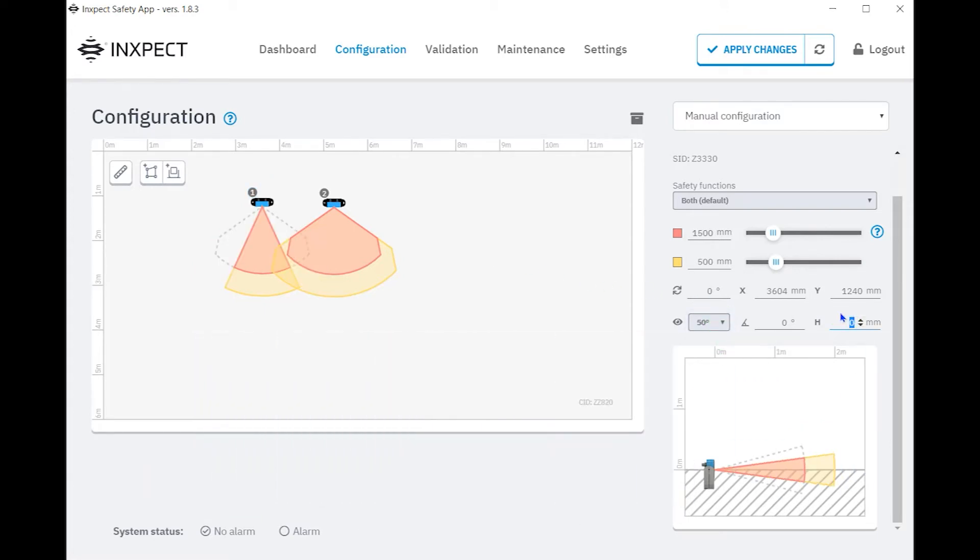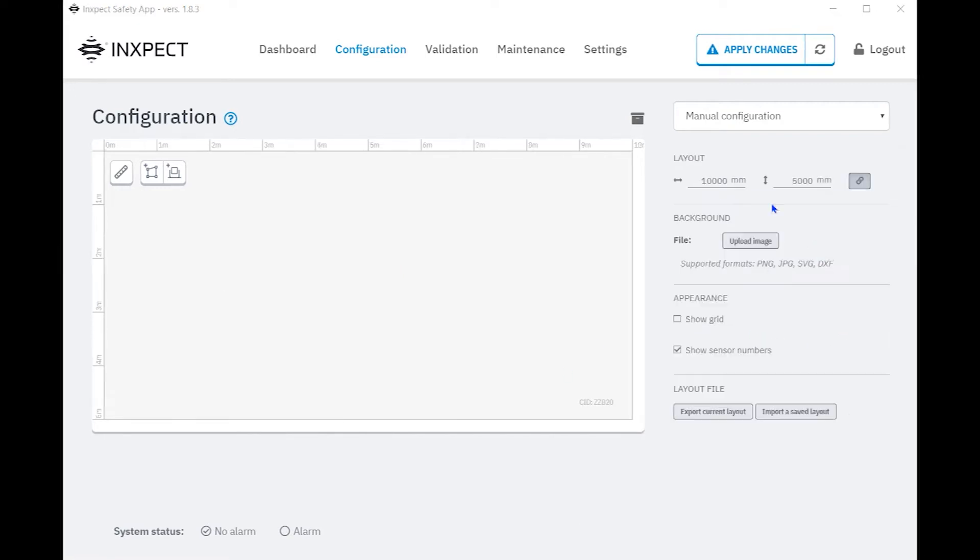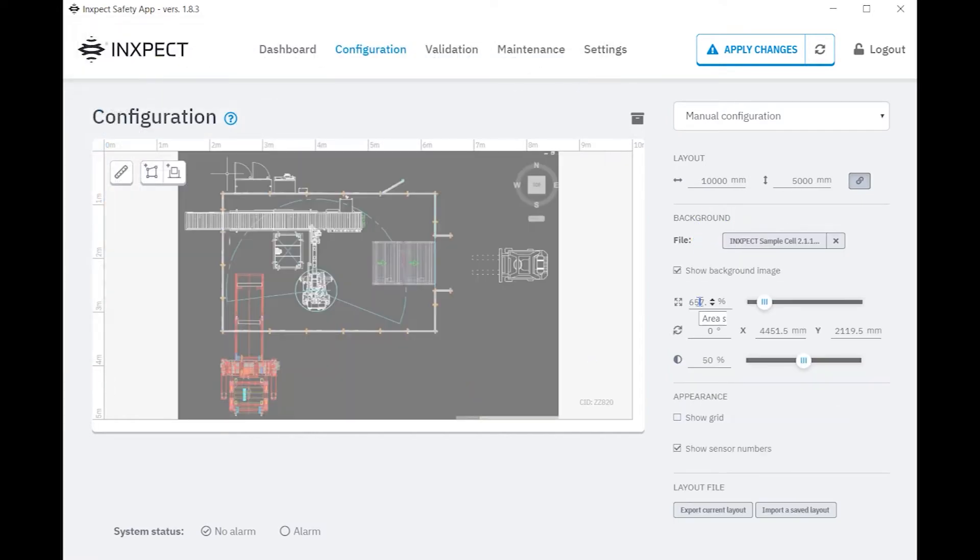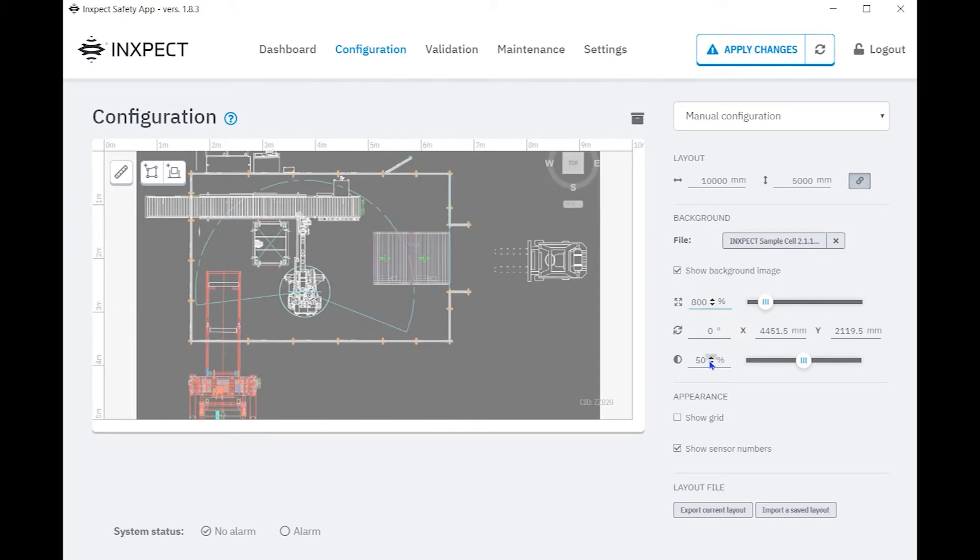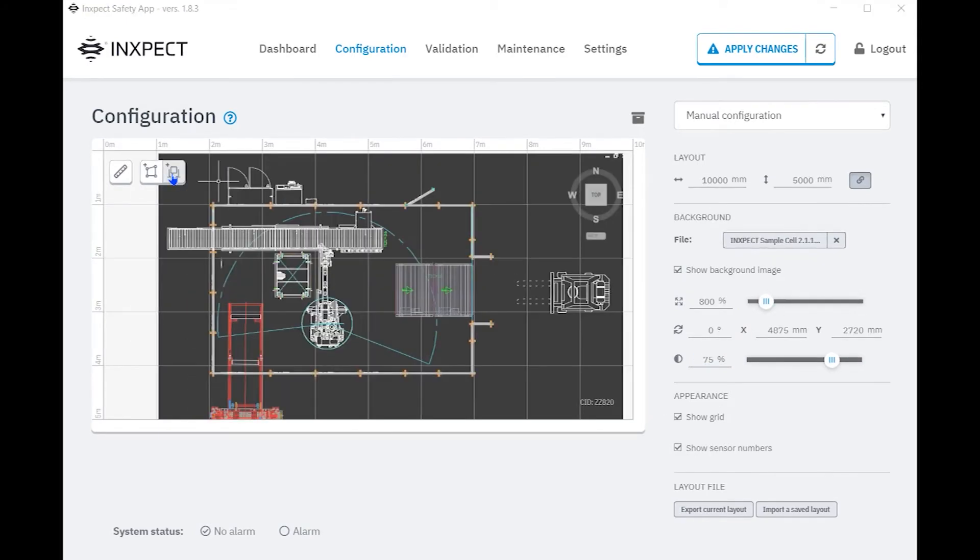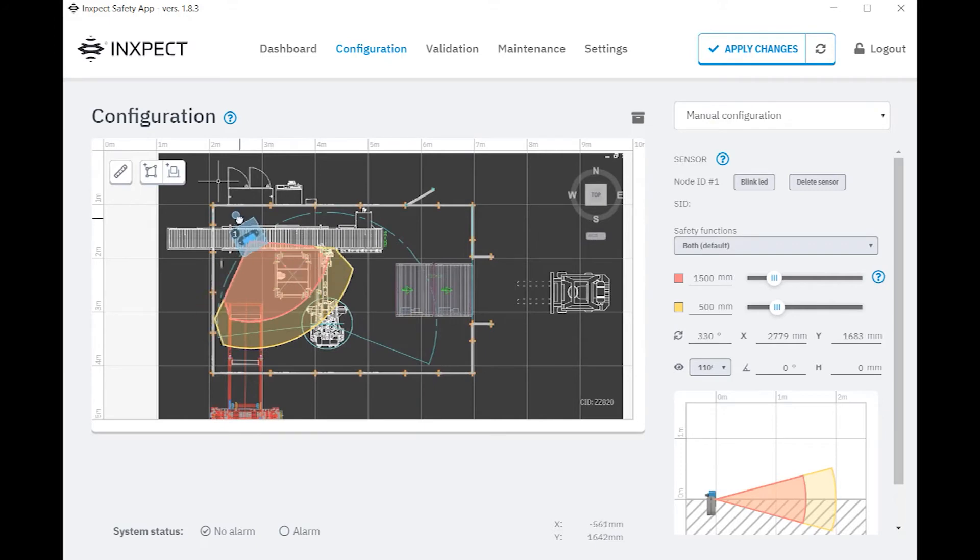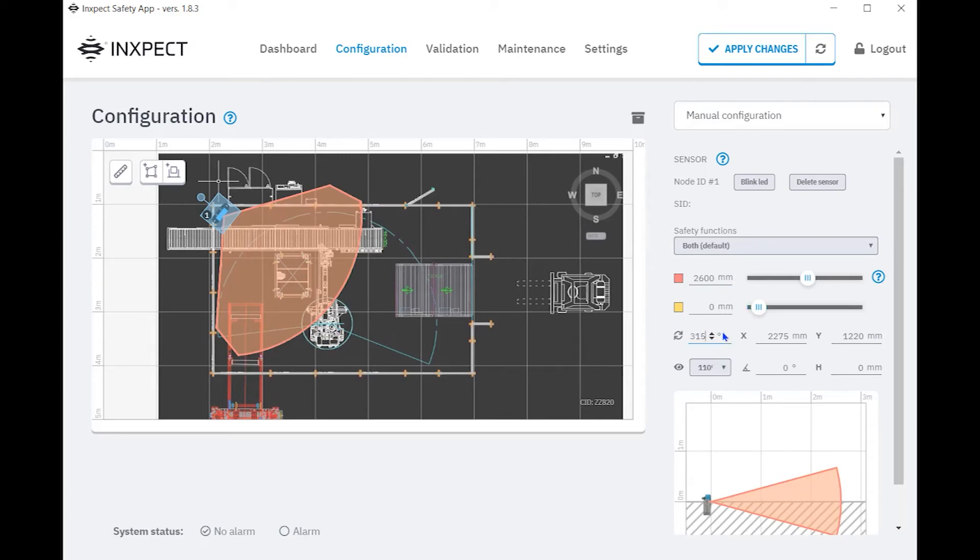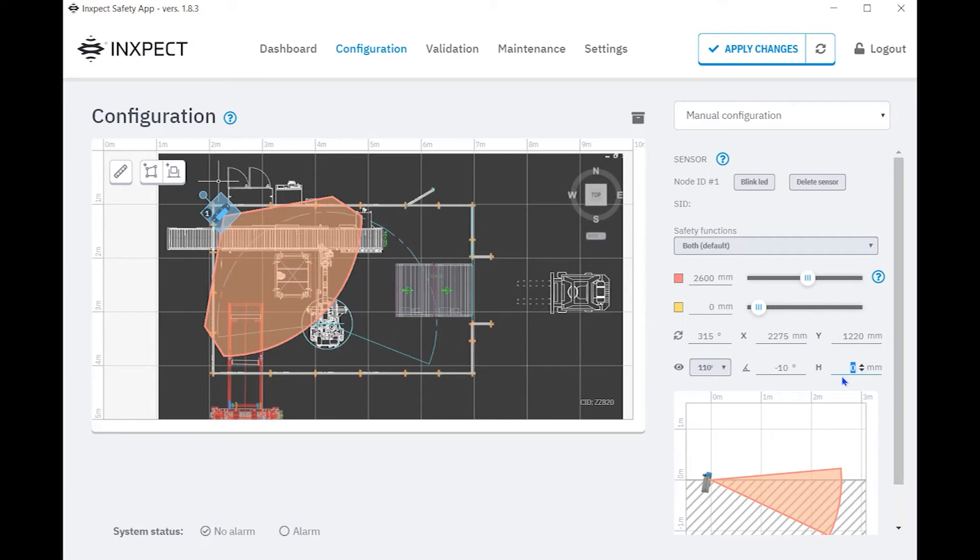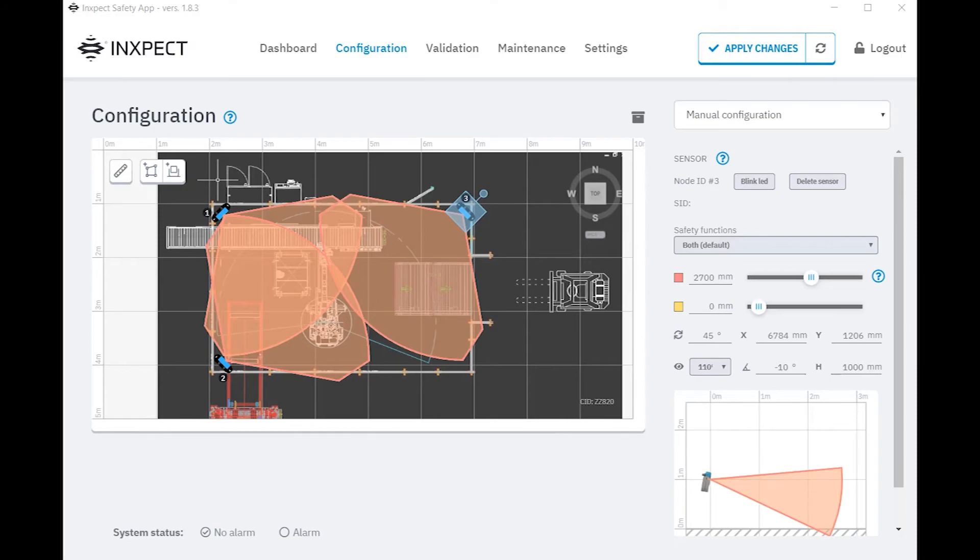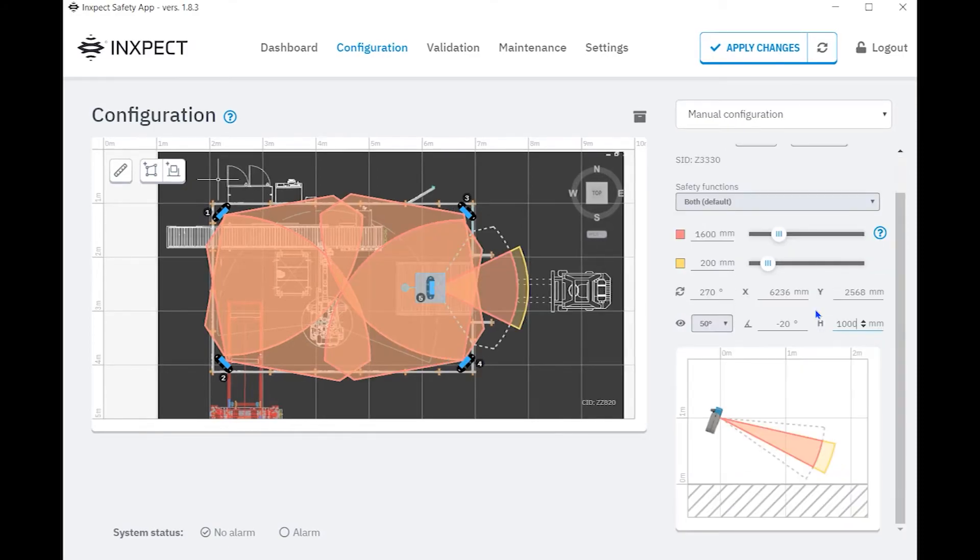The inclination angle and height can be changed by entering the desired angle and height required for the application. A nice feature worth pointing out is the ability to import an image or drawing file into the configuration. The image can be a simple JPEG or DXF file. The software provides the ability to properly scale the drawing, which will be important for good representation of the sensor's field of view. This can be a good reference tool to identify how many sensors may be needed, positioned, and configured to provide adequate coverage for the area to be protected. An example using this feature may look something like this.